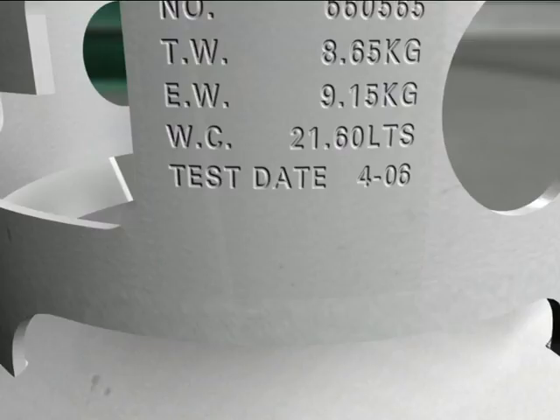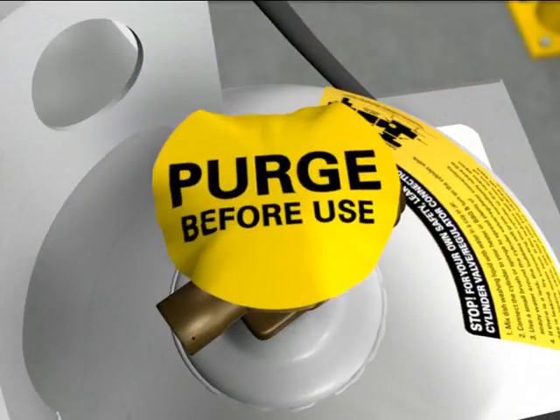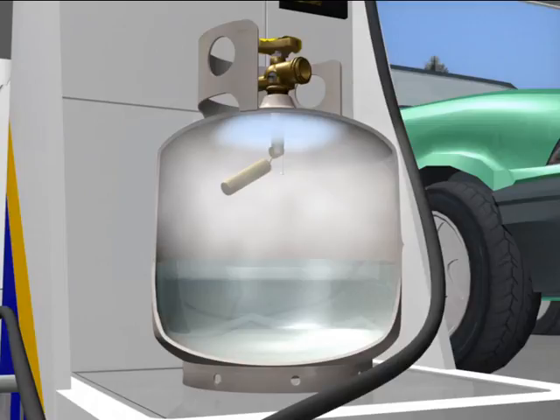If you check a cylinder's manufacturer and test dates and find it's new or has just been tested, you will need to purge it. This is because it may contain air or nitrogen which will prevent the LPG from igniting when first connected to an appliance.